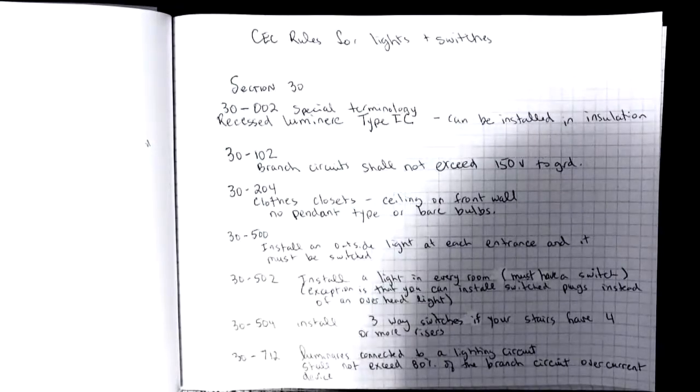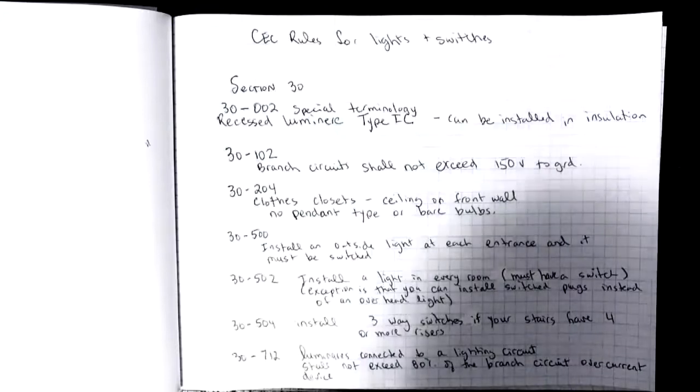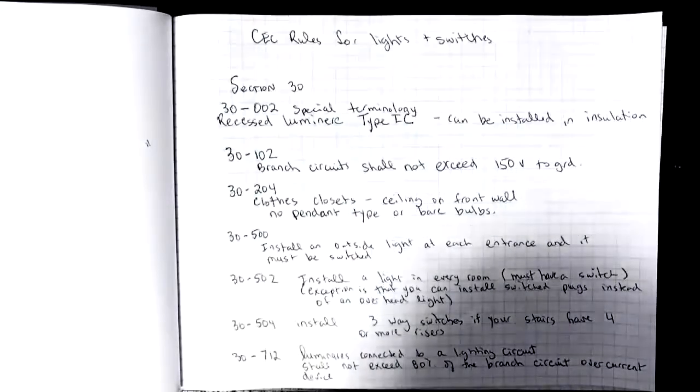The rule itself says luminaires connected to a lighting circuit shall not exceed 80 percent of the branch circuit over current device. Now there are some other rules in section 30.